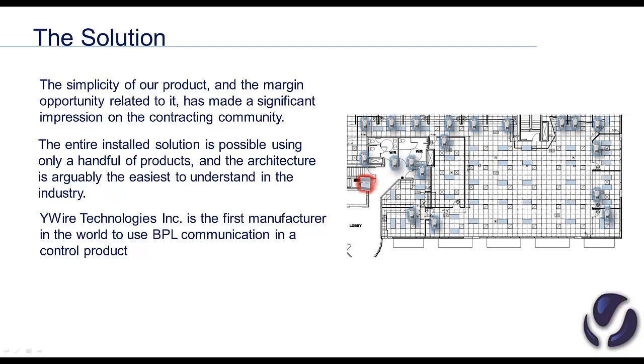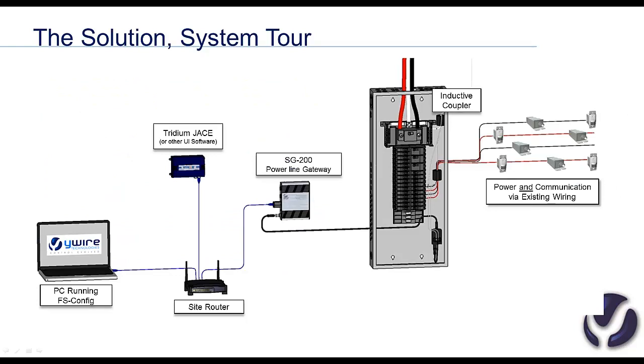Also important, many customers are focused on the fact that our installs are complete in days instead of months, and the fact that there's no damage caused to the existing building during installation. This all combines to cause minimal disturbance to the building's occupants. YWire achieves all of this with a simple, clean, easy-to-install system that is warranted for 3 years. Seamless connectivity with almost any energy management system is possible with both the Niagara Framework products or through our fully graphical BACnet gateway. Free software commissioning tools and off-the-shelf system components allow our partners to offer an innovative, cost-effective solution to their customers.